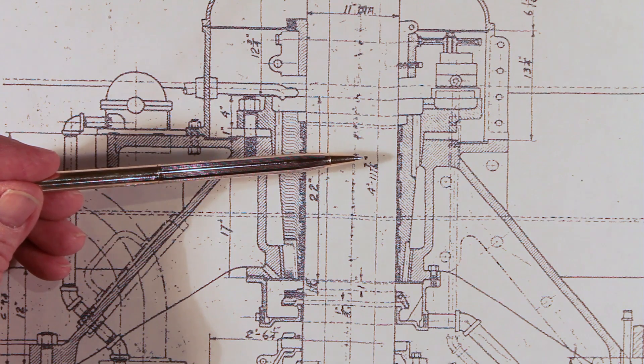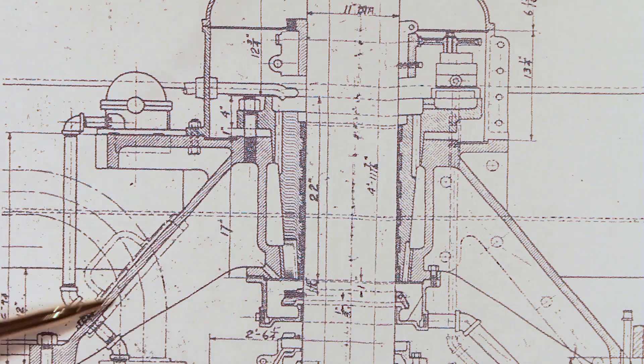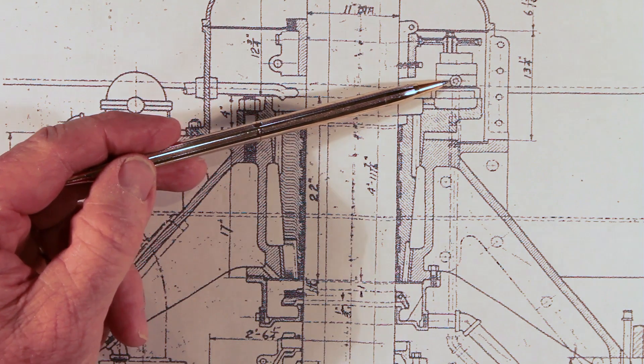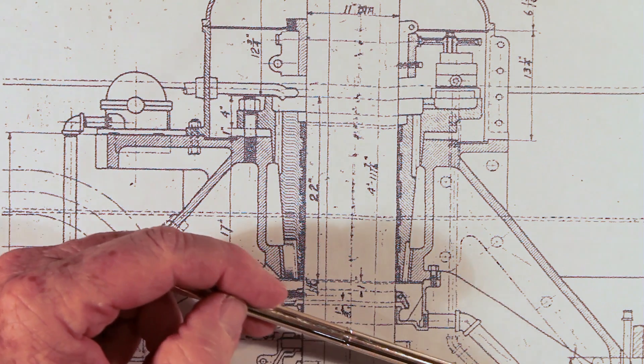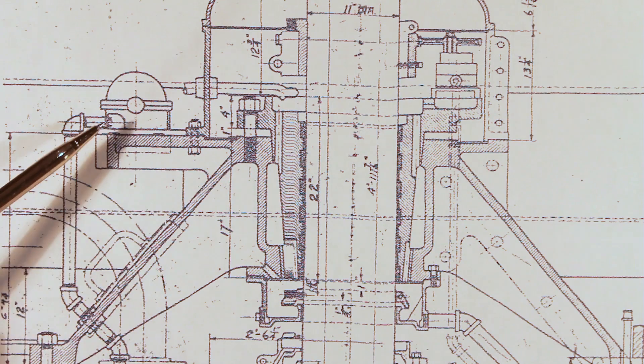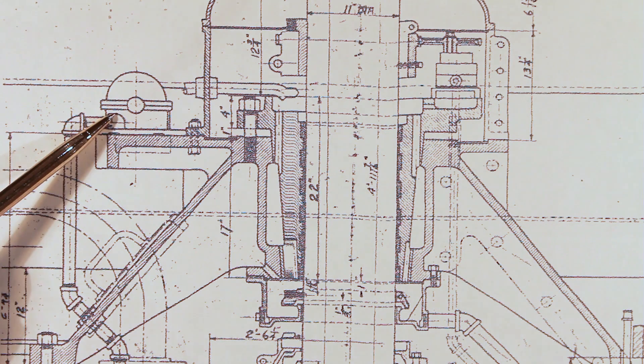The conversion plan involves removing the bearing and oil pump assembly mounted above the turbine head cover. The existing white metal bearing is contained in a cast iron carrier. This gear pump supplies oil to the lower bearing; oil flows downward through the bearing past the slinger ring and into a containment area of the head cover, where it is conducted by pipe back up to the pump above the bearing. In addition to this shaft-driven gear pump, there are two additional external electrically driven oil pumps that will continue to supply oil to the upper guide bearing and main thrust bearing at the generator level, but not to the converted lower guide bearing.